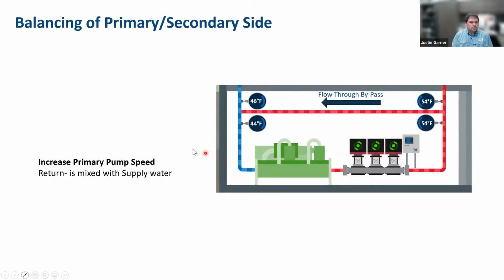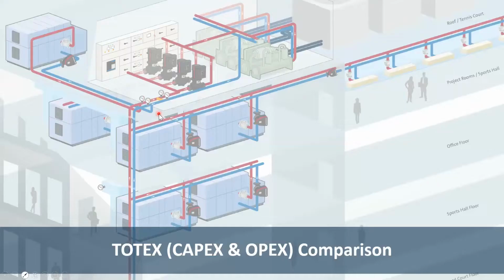The last condition is that our return is being mixed with our supply water. So we've got return water coming back here. We don't have enough pump speed. Basically, we don't have enough flow in the primary. So we're returning it back here. It's being reflected in this temperature sensor on the supply side. And we'll know now to increase our pump speed. The building is opening up, more zones are calling, more loads are calling. So we'll pick up pump speed to satisfy that. And that's really it. That's as simple as it gets when it comes to the different operating conditions.